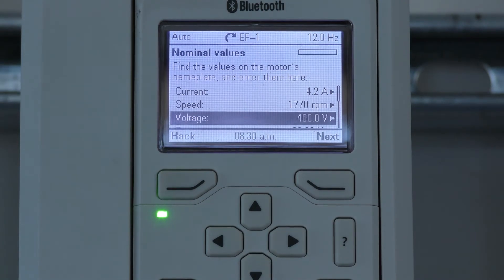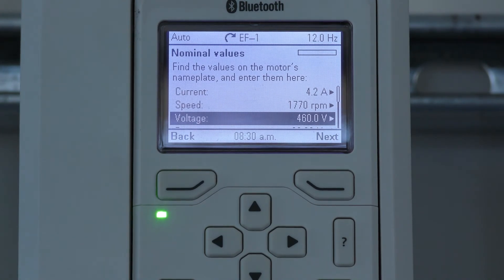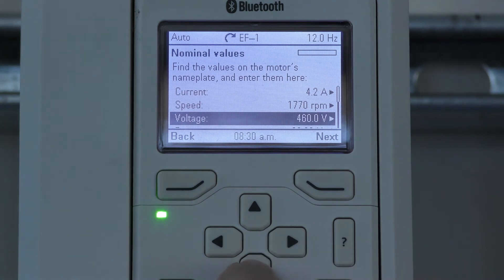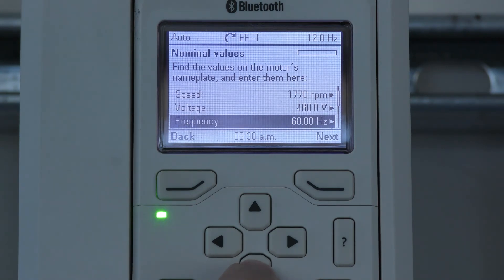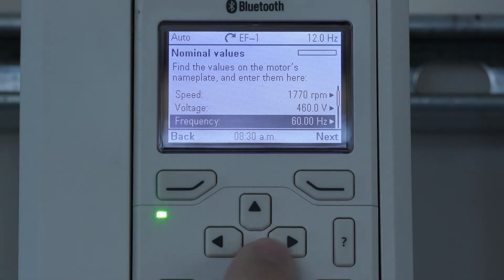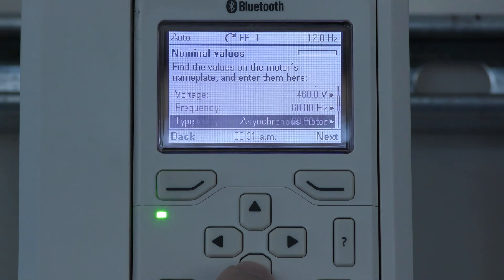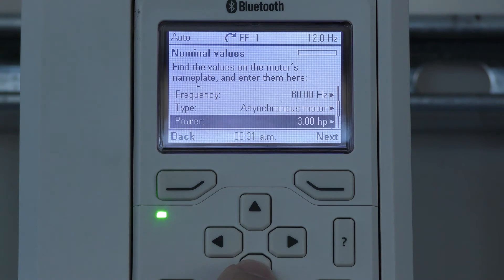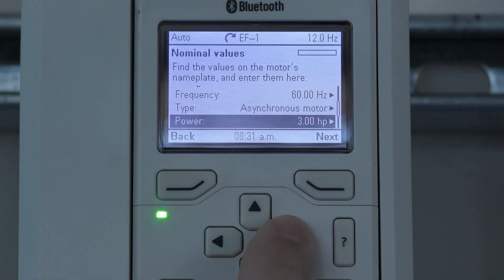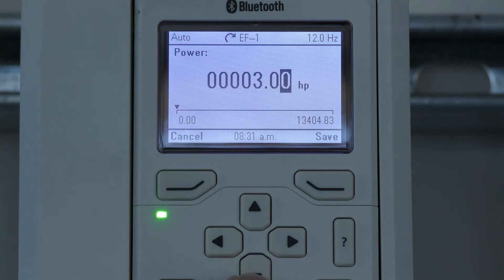Voltage: 460 is typical of most motors and does not need to be adjusted, even though utility is around 480 volts. Frequency is also the same at 60 hertz and does not need to be adjusted unless different on the motor nameplate. Power only needs to be adjusted if different on the motor nameplate.